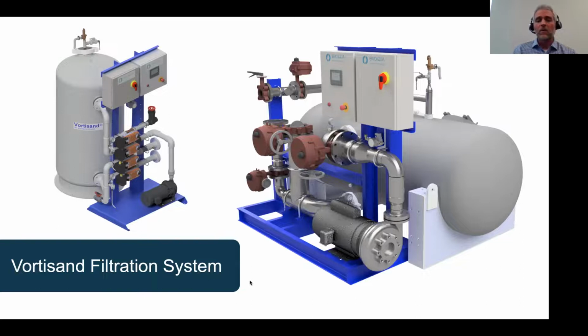Okay, lastly, we're going to talk about the media filter called the Vortisand Filtration System. And this technology is really built for the utmost asset protection, really for customers looking for the most mission critical asset protection. Because for those of you who are constantly, on a daily basis, monitoring approach temperatures, looking at the kilowatt hour or amperage draw on your motors in your cooling towers, or your chiller runtime, right? This is the technology that ultimately will provide you with the highest level of protection.